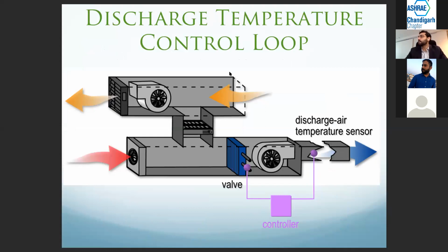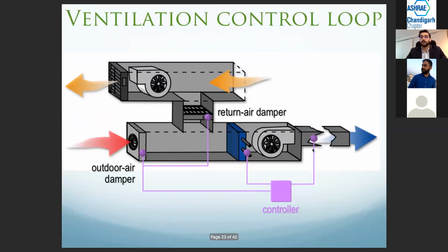This is a discharge temperature control loop. In this scenario, in this air handling unit, we have a discharge air temperature sensor, which is an input into the controller, and it sends an analog input to the controller. The controller says, okay, I need to decrease the temperature because it's too hot and I don't want it this hot. So I'm going to tell this valve to open up, let more water flow through the coil, and that will cause the temperature of the air to go down, and we will be able to satisfy space temperature. That is a classic example of a very basic and simple control loop. Now we'll keep on building upon that, right?